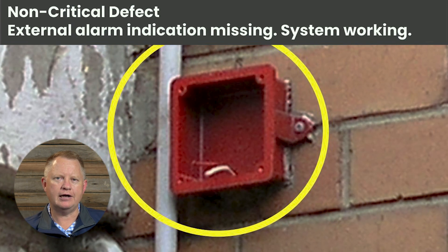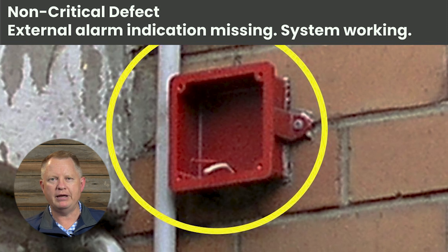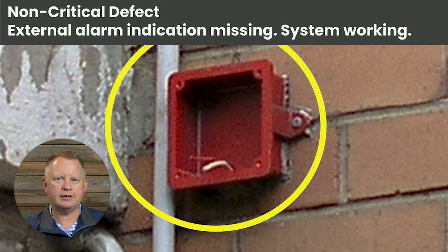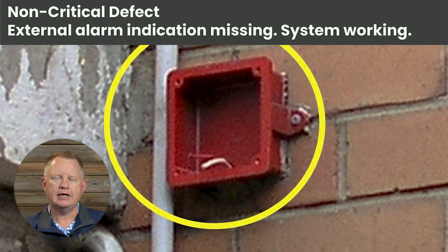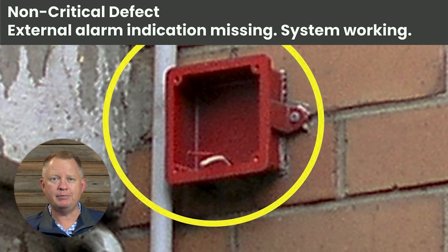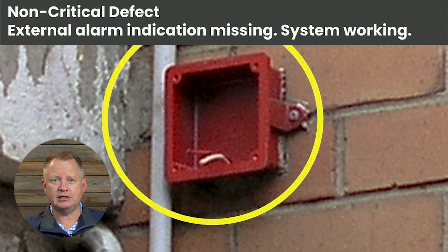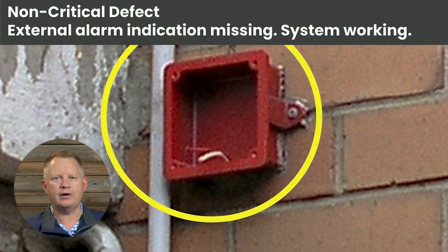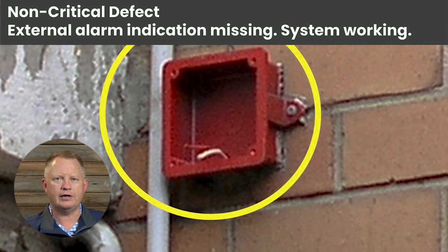This is an external warning device or external bell. I'd call this a non-critical defect because the rest of the fire alarm system would still operate. This would be contentious for some people, but in my perspective it's a non-critical defect because the operation of the fire systems within the building would still function correctly.